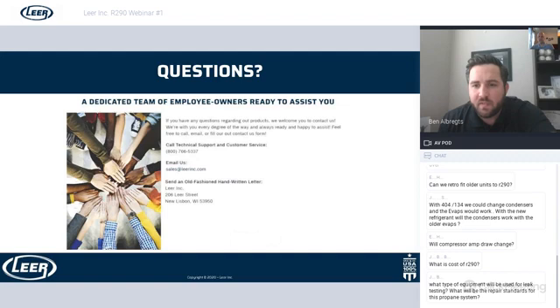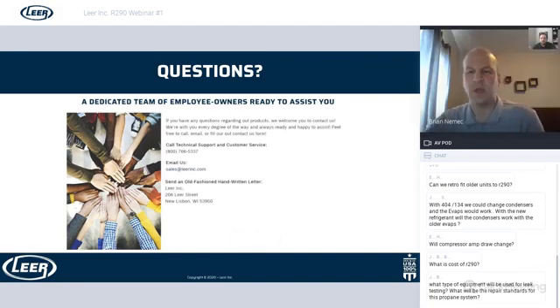What type of equipment will be used for leak testing? What will be the repair standards for the propane system? Brian, you want to take that one? Okay, for leak testing in our factory, as I mentioned, we're doing a helium leak test prior to charging.